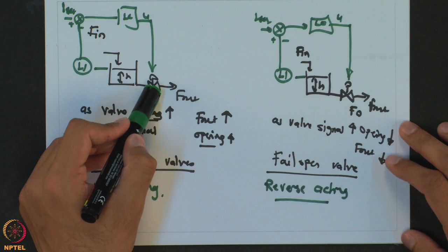You can see that same system, only difference is the actuator type. In one case the actuator is fail close, and in the other case the actuator is fail open. Just this small difference is going to make the controller to be either direct acting or reverse acting. And as I had said earlier, if we mistakenly use this to be a direct acting controller, it will never be able to maintain the level. And as we look at the control systems, we will see why that is the case through a more mathematical analysis as well. So, it is very important to know what is the type of the controller action.